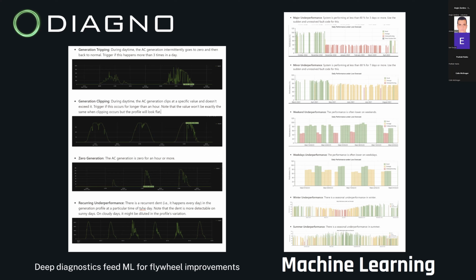So here I'm showing a few examples. On the left, it's the level 1 AC faults—you can see the second chart down shows inverter clipping, and the fourth chart down shows afternoon shading. On the right, we've got deeper level diagnostics grouped into categories. You've got severe underperformance that might occur because an inverter goes completely out, and weekend underperformance, which might occur because of zero export systems with low consumption on weekends, etc. These are all things a machine learning algorithm can detect, categorize, and present, saving significant resources going forward for our customers, O&M personnel, and asset owners.